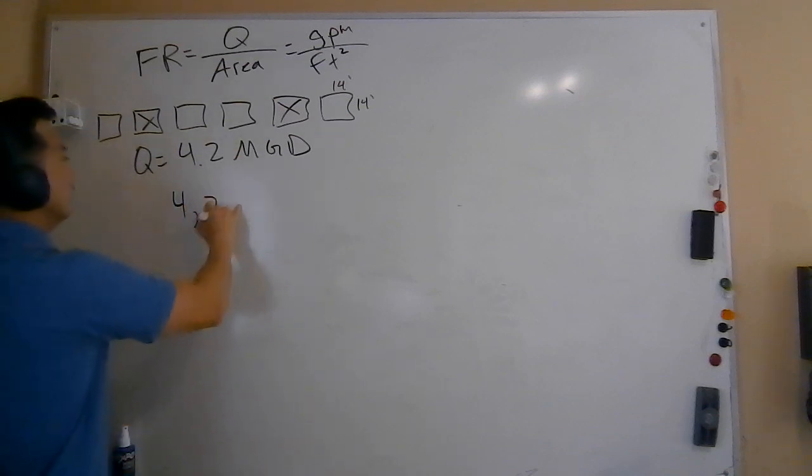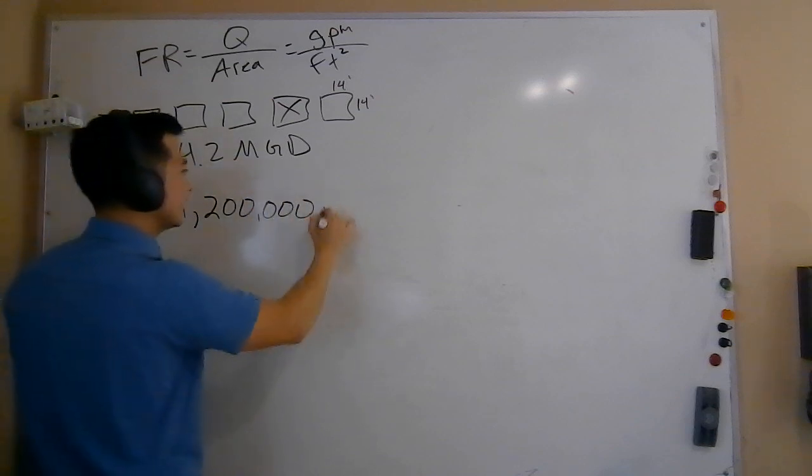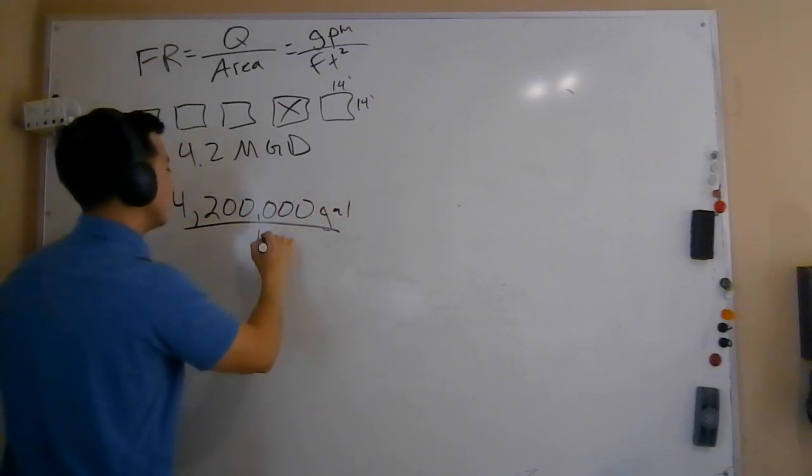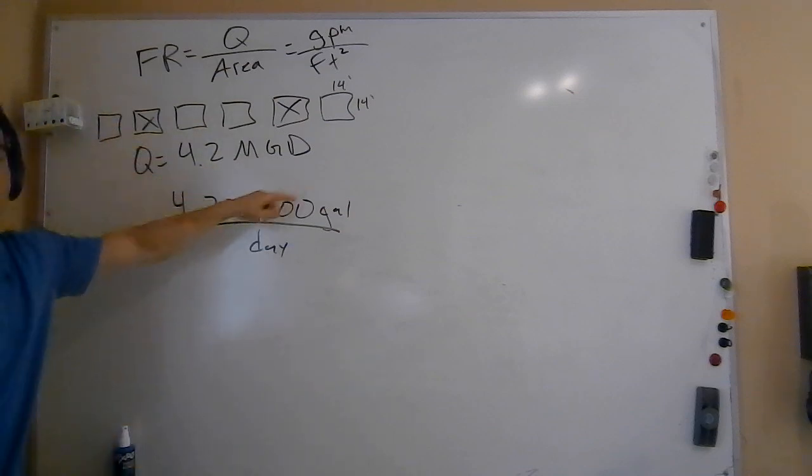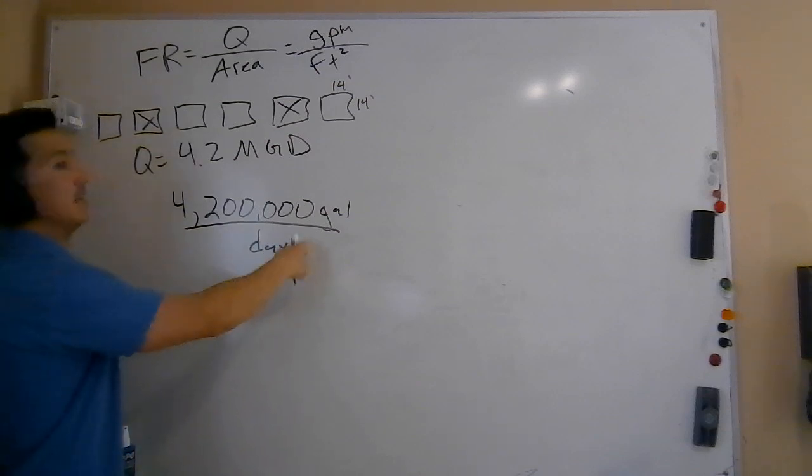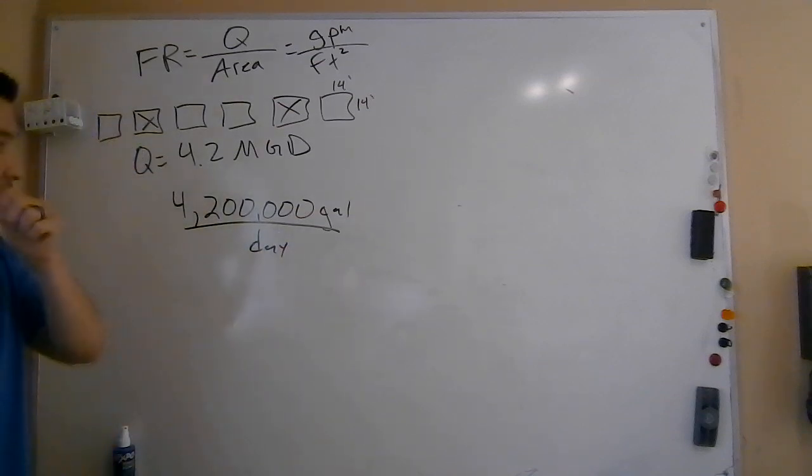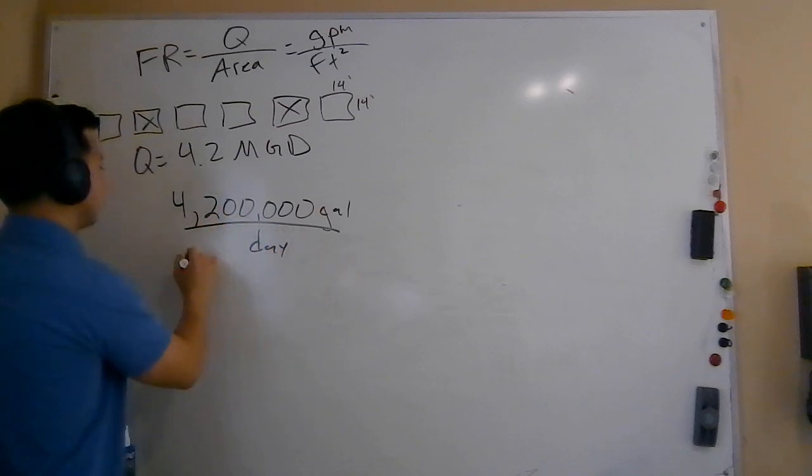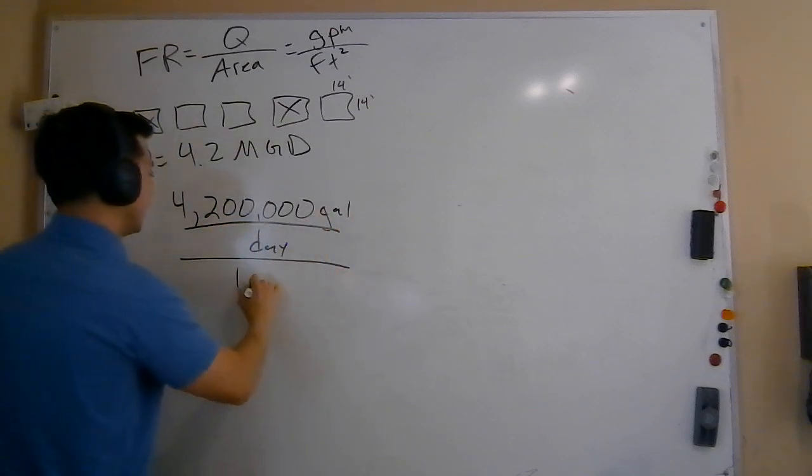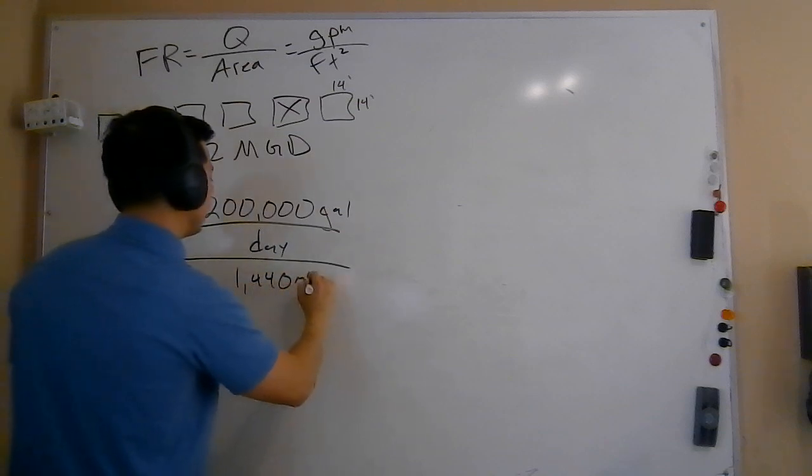So we got to do a quick unit conversion. In this case, we're going to do 4,200,000 gallons per day, right? That's what this essentially is saying, 4.2 MGD. Let's write it out as gallons, 4,200,000 gallons per day. I need it in gallons per minute. So instead of days as my unit down here, I need to figure out what is this in terms of minutes. How do we convert from day to minute? If you look at your formula sheet, or remember there's 1,440 minutes in a day. So what are we going to do? We're going to take this, we're actually going to divide the 4.2 million gallons per day by the 1,440 minutes per day.